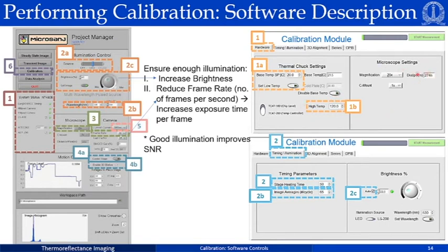Okay, the microscope settings will be carried over from the project manager settings, and you cannot change it here. If you notice one more thing, there's a number called distance per pixel. So this will give you an idea of the temperature information, that is, over which region you are averaging the temperature. For example, 274 nanometers means that one pixel houses the information of a 274 nanometers by 274 nanometers area. So it will give information of the temperature averaged over one pixel of this 274 nanometers value. Higher magnification means the distance per pixel would reduce.